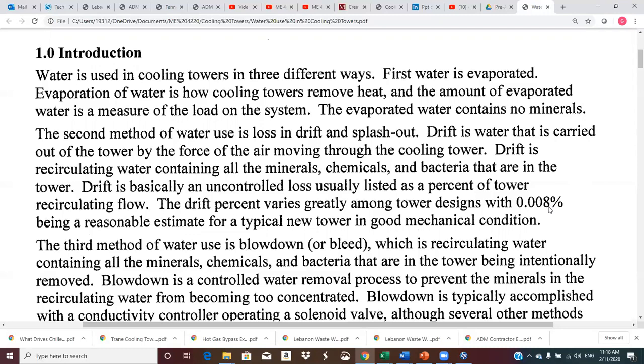0.008% as a reasonable number for a new tower in good mechanical condition. And that's a percent, not a fraction. So we've got to add 2 more decimals to that before we multiply.